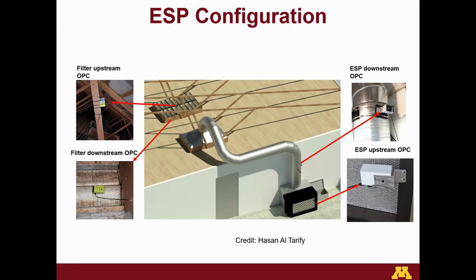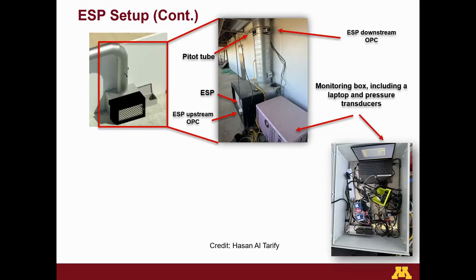So another diagram: at the ESP unit here, our upstream OPC, or optical particle counter, is placed here, our downstream right here in the duct. And for the filter box, the upstream OPC is on the truss, and then the downstream was in that filter box below the filters. So we're able to count particle ratios of incoming air and downstream air for both technologies.